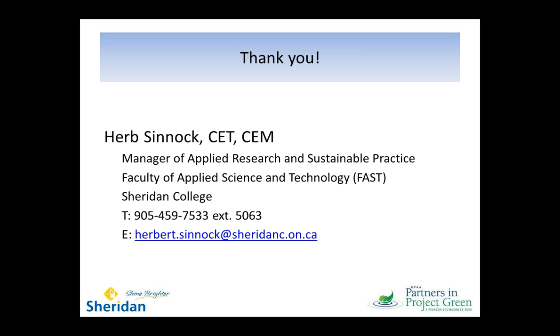Okay, yeah, thanks for that. That's good. It's not something I addressed when I was talking about variable frequency drives in the presentation. Variable frequency drives are electronic controls. They're going to inject a bit of noise into your system, and not all motors are really able to handle that noise properly. In some motors, that's going to cause excessive heating or vibration. So there are motors that are rated for inverter quality that are basically well suited to that kind of drive, and some of your motors are going to do perfectly fine with that. This is a conversation you can have with your suppliers, manufacturers, vendors about what kind of compatibility you've got between drive and existing motor, or whether a new motor needs to go in. So yeah, that was an excellent question.